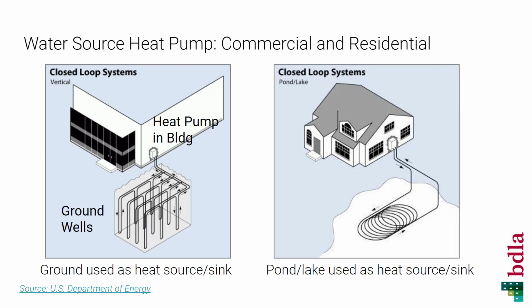The next option for heat pumps is a water source heat pump. These are commonly ground paired, sometimes referred to as geothermal, but more technically correct is ground source heat pump. These have entire loops of water, usually mixed with a small amount of refrigerant or antifreeze, which circulates throughout the ground, and the ground is actually used as a heat source or a heat sink. Heat from the building is either pumped into the ground or extracted from the ground, and it can be stored seasonally. If a building is being cooled all summer, the ground heats up, and then in the winter, when it switches to heating mode, it pulls that heat out of the ground and puts it back into the building. This is a really effective and efficient system, particularly in climates with big swings, so very hot summers and very cold winters.